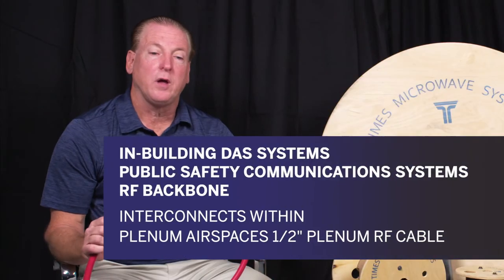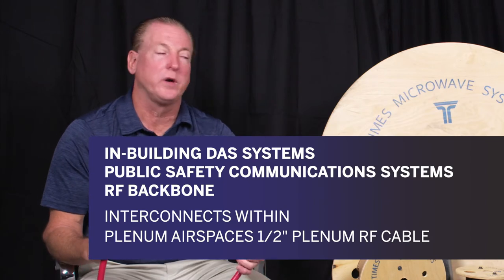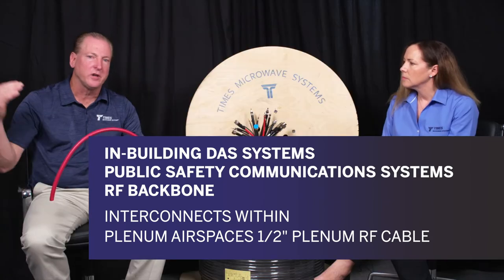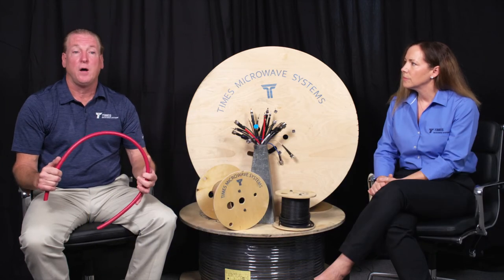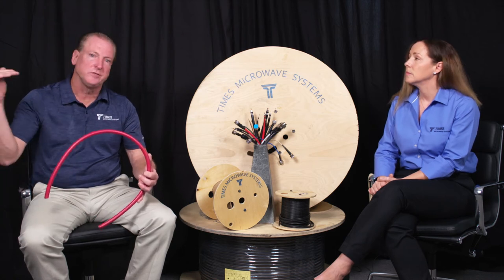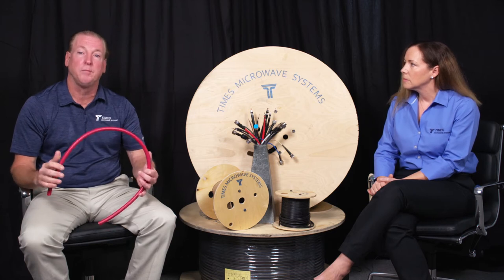In most building applications, a lot of the cable is run in the raceways or air return handling ducts because it's a nice, easy way to lay cables. What they found over the years is in the event of a fire, the air return handling duct acts as a big billow and sends smoke and flame racing through a building, which is obviously a big concern.